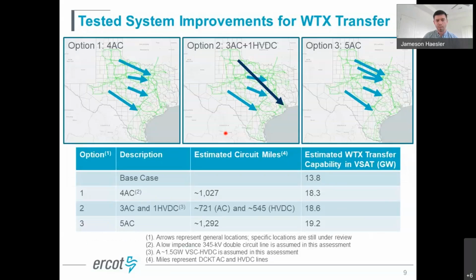Just to touch on that a bit more: both AC options, 1 and 3, increased congestion coming into Houston. When you look at the map, it's a little clearer why that is, because there's this large transfer from the west, but it stops in the DFW area and isn't able to make its way down to the Houston load center because of that interface limit, whereas option 2 is in a sense going straight to the load and able to bypass that northern Houston constraint.